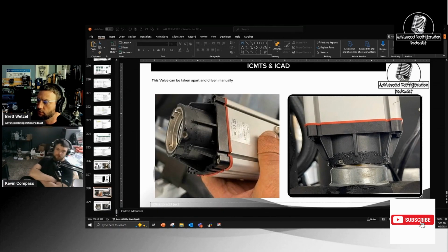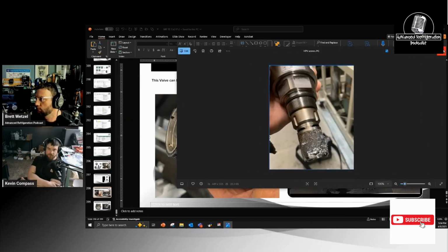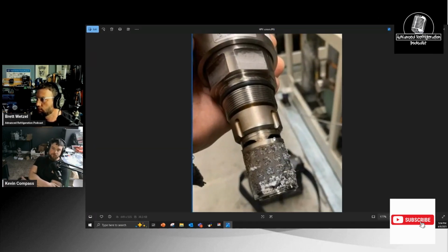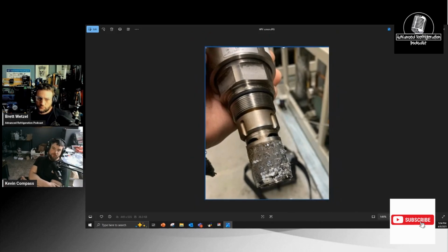They're metric, of course. 1, 2, 3. So there's 3 metric Allen screws there. Don't lose them. Take them all the way out. Put them in your pocket. And then when you go to take this thing off, there's O-rings underneath there. So you're going to have to wiggle it back and forth, wiggle, and then it'll pop off finally. Once you get the head off, don't worry about it burning up or anything like that. There it is. So once you go to spin this thing out, that's a CCM valve, but same type of deal. So you have this screen here.